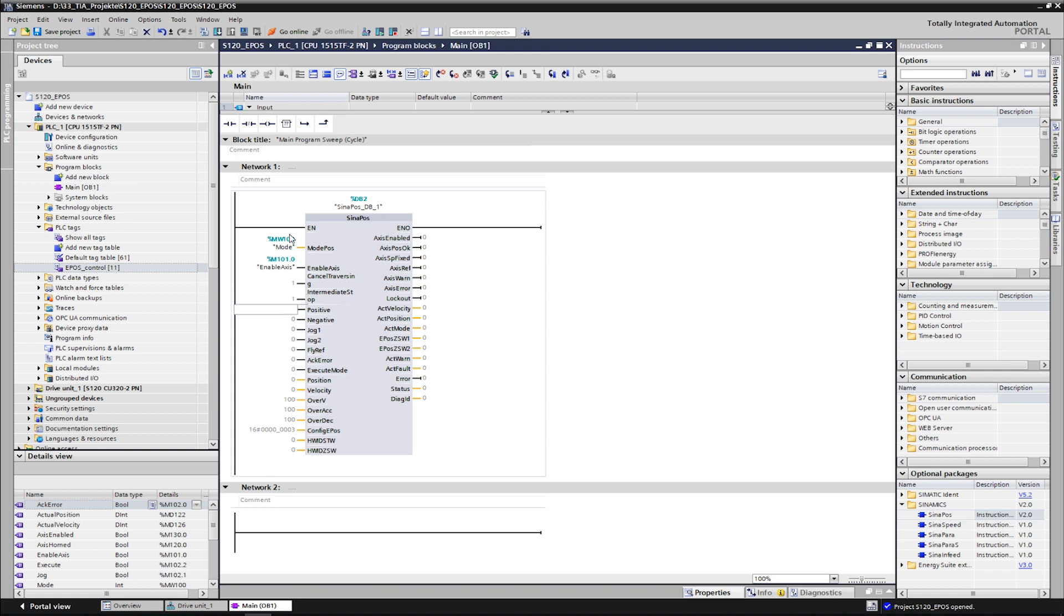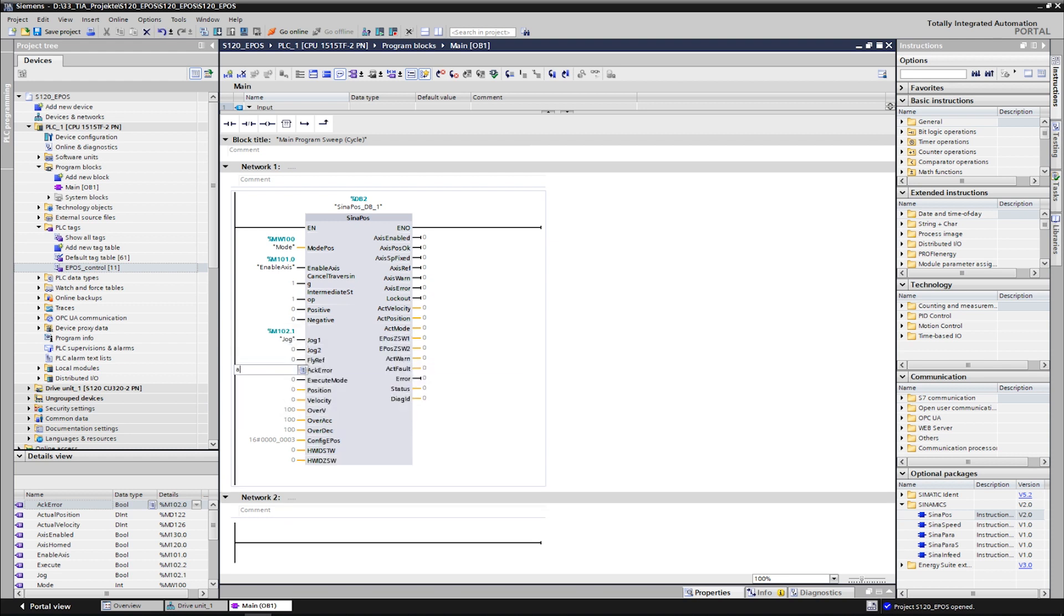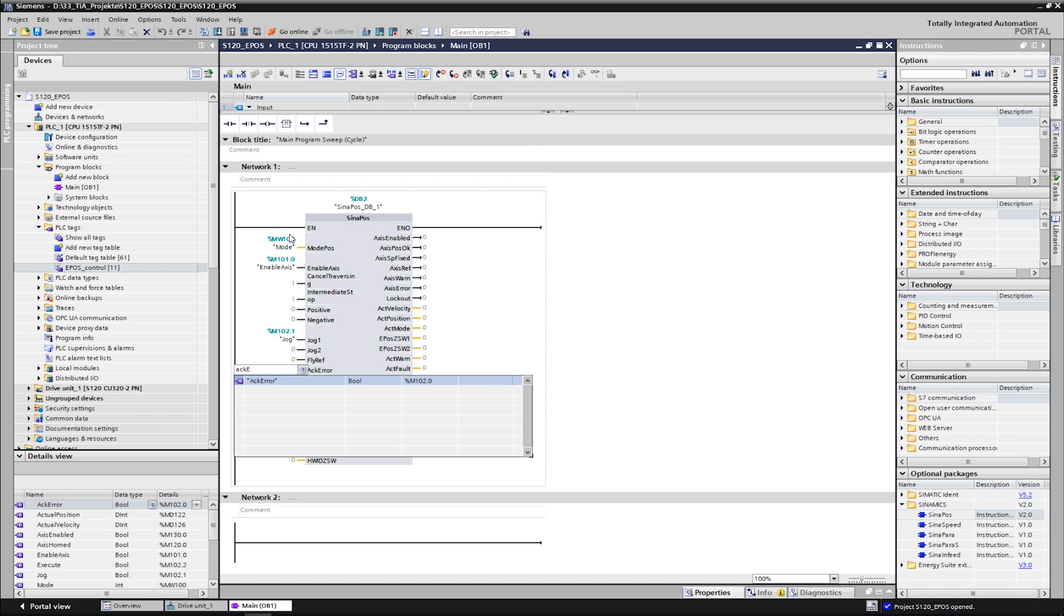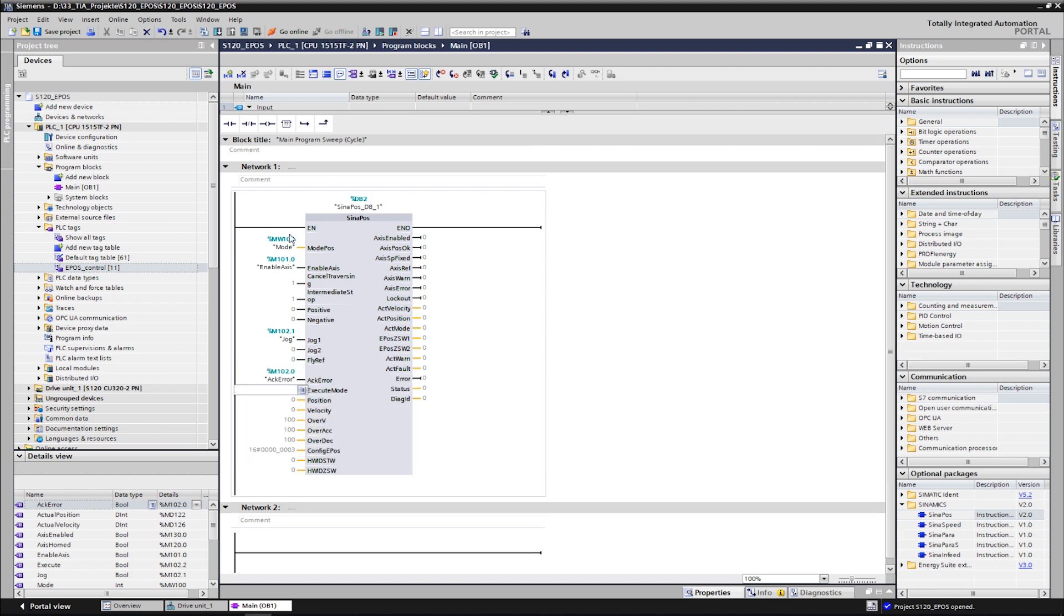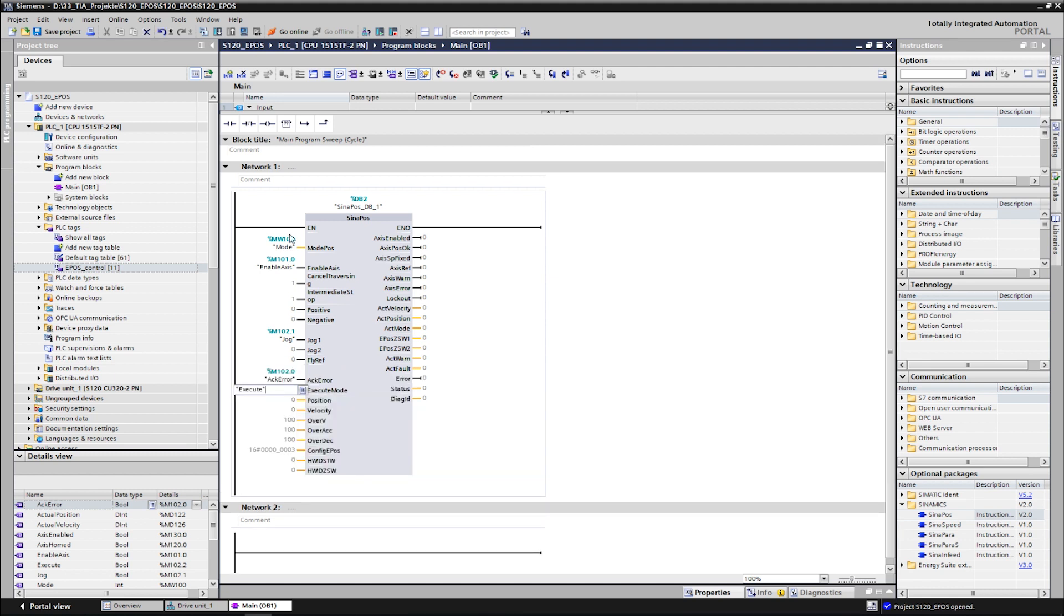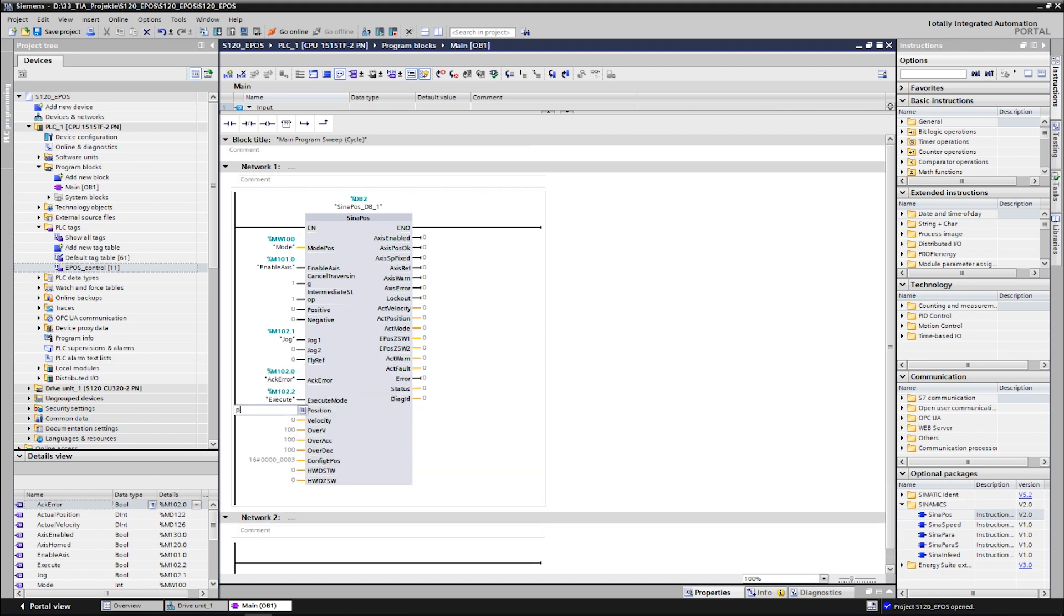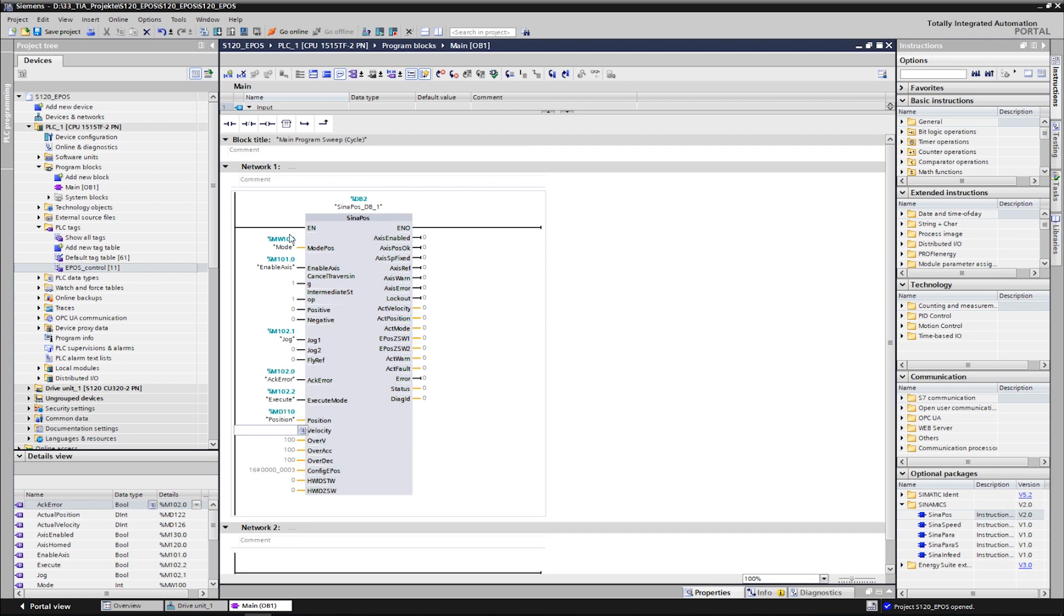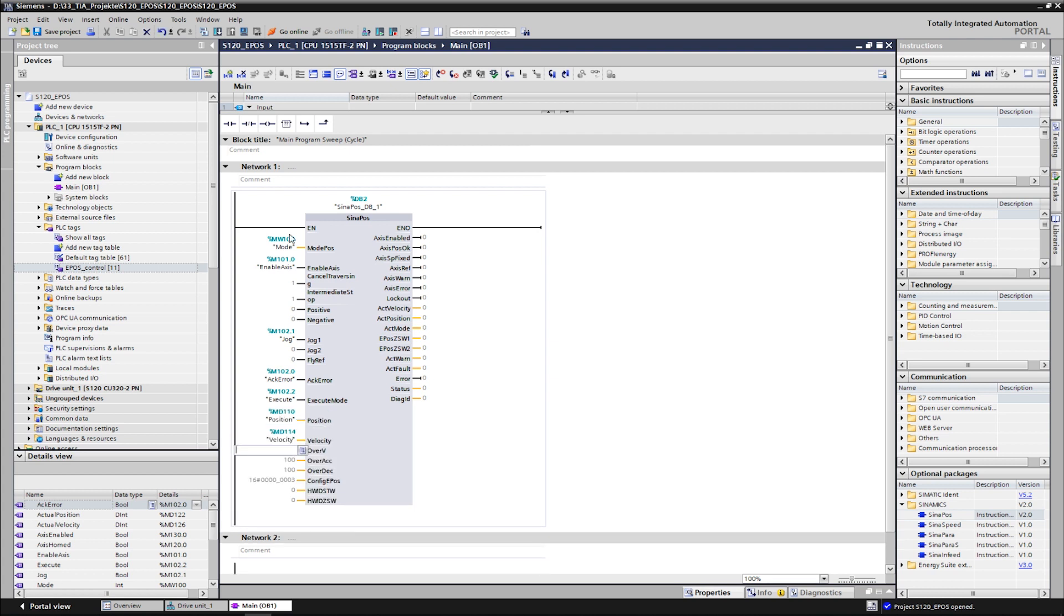JOG stands for the jog function. AcknowledgeError can be used to acknowledge any pending errors. The input ExecuteMode starts the selected job. The inputs Position and Velocity define the positioning movement. The overrides for speed, acceleration and deceleration are defaulted to 100%, which we leave as it is.